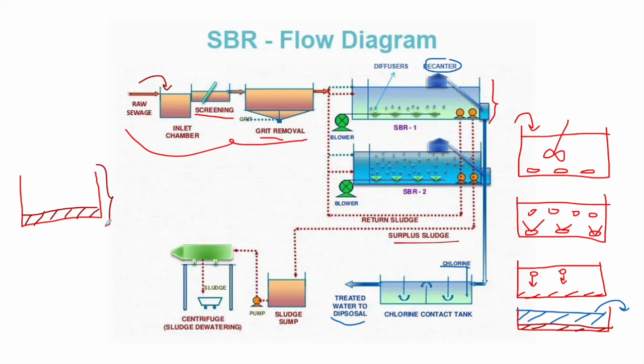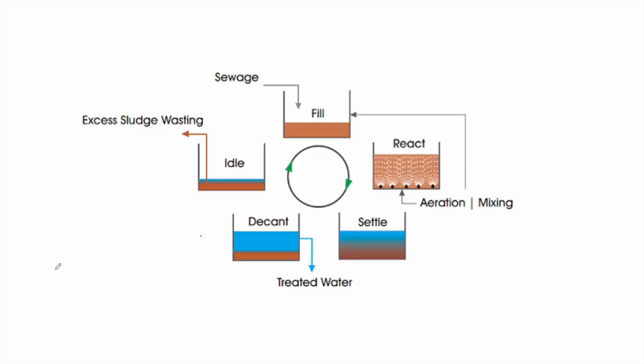To summarize, one full SBR cycle has five steps: the fill stage to receive incoming wastewater; the react stage to introduce oxygen through aeration and mixing; the settling stage for flocs to settle by gravity; the decant stage to remove treated water for tertiary treatment; and the idle stage to remove excess sludge and provide a brief operational break.